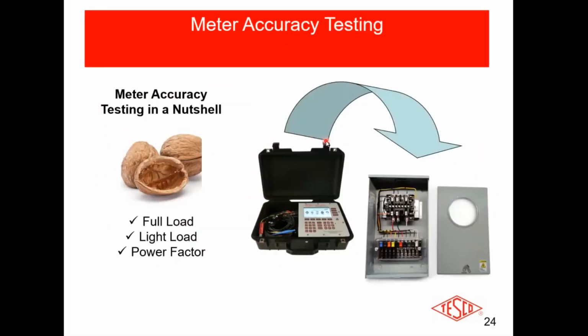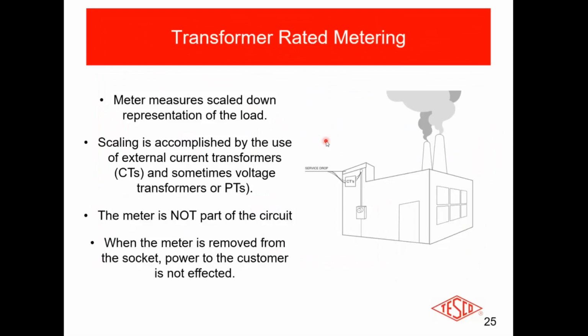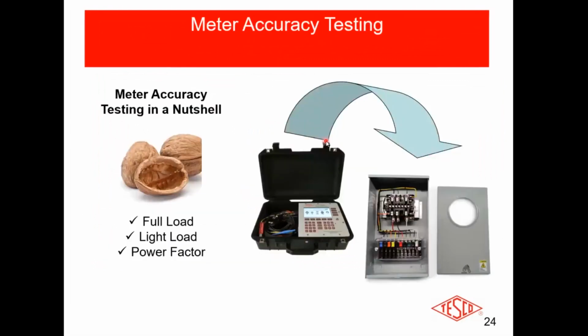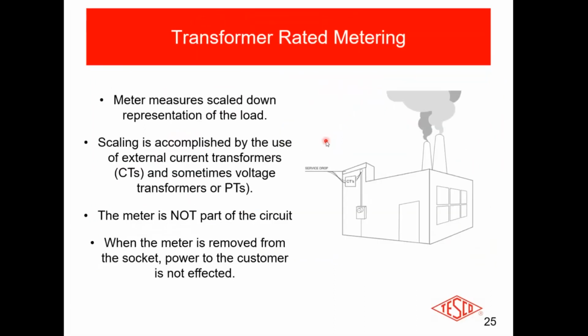Okay? Meter accuracy testing. When you're out in the field and testing your meters, typically you're doing 3 tests: a full load, a light load, and a power factor. And whether you're doing that in the field or in your shop, those are your standard 3 tests. Okay? Now, let's jump into transformer-rated metering real quick and how that differs before we get too far into testing.